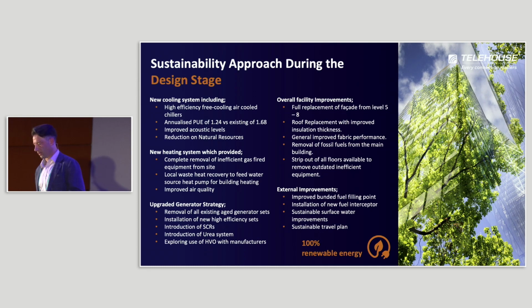The architect at the time kept the building very fluid. So that was one of the points that we hit on in this: reducing 3 of the riser sizes to maximize white space and serve the building through 2 risers in the front in the technical areas. Through design stages with Black and White, our design partners, we now have a new cooling system in the building which is being deployed at the moment. It's currently under testing. Highly efficient free-cooled air-cooled chillers, annualized PUE of 1.24 versus the existing PUE of 1.68. So the sustainability factors coming in here include not knocking the building down, repurposing old plant and equipment, and removing all of the old, really heavy gas-fired generation, which you'll see now.